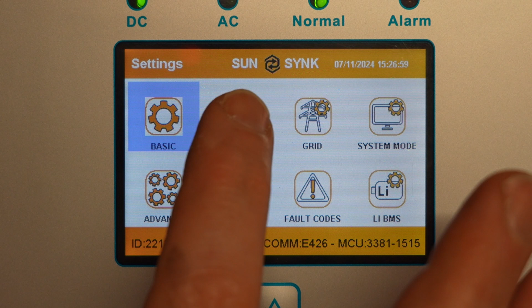So first of all, let's go into a menu and have a look at our battery page, see what's relevant here. Number one, we're going to have lithium ticked. Then we'll have CAN bus communication, which should already be ticked as standard. Communication protocol will be 0 for the Seplos BMS. And then we've got battery capacity, which it will read from the BMS, and charge amps. Now we can set that, and that does actually have an effect on the battery. You can limit your charge amps via this page for each battery that you have connected. Even if they're in parallel, that will set each of them to charge at that amperage. As it turns out, it tends to set the master to that level, and then the slave battery, if you have two batteries connected, will either lead or lag depending on what its voltage is until it catches up.